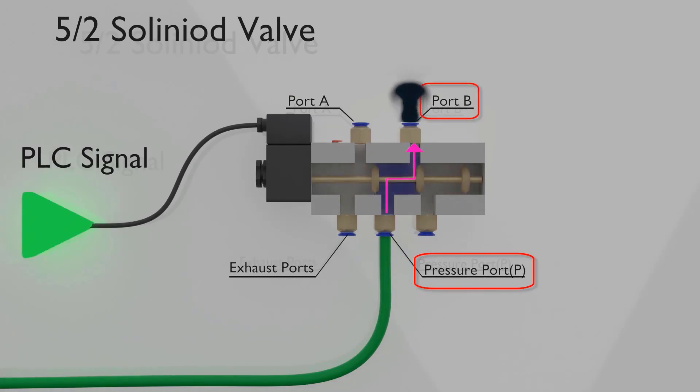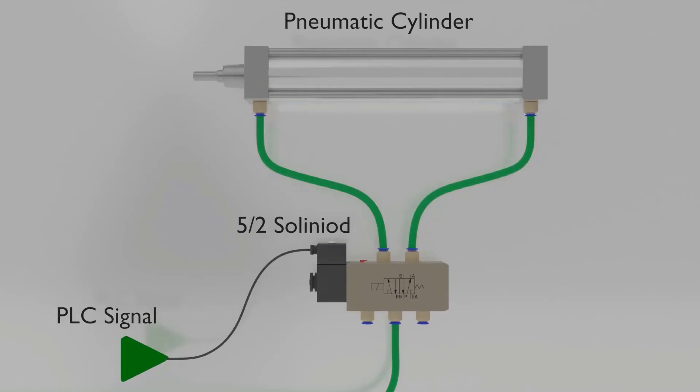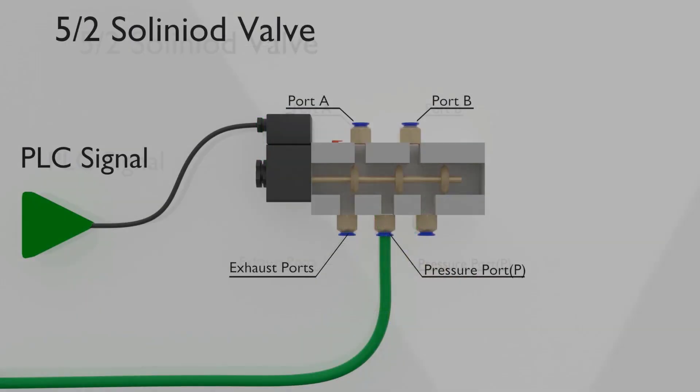Spool moves when solenoid coil is energized by the signal coming from the PLC. This PLC signal is a digital signal which is either on or off. There are other ports in the solenoid which are exhaust ports. We will explain what are these ports shortly.